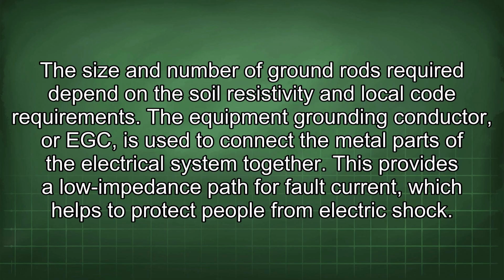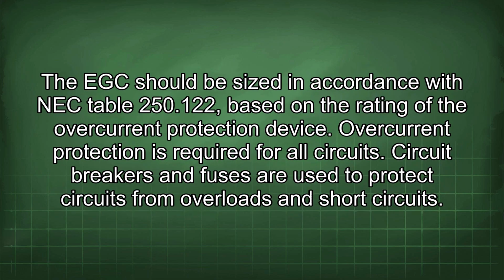The equipment grounding conductor, or EGC, is used to connect the metal parts of the electrical system together. This provides a low impedance path for fault current, which helps to protect people from electric shock. The EGC should be sized in accordance with NEC Table 250.122, based on the rating of the overcurrent protection device.